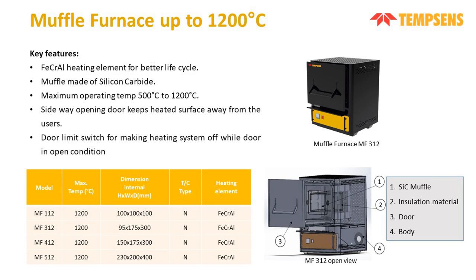Then you can see in the image the MF312 open view. You can see we have a door opening to the side of the furnace with a limit switch for safety reasons, to shut off the furnace when the door is open. And coming to the models, we have four models in the muffle furnace. Majorly the models are differentiated according to the dimension. The temperature is the same for every unit; its maximum is 1200 degrees Celsius. The thermocouple we have used in the muffle is an N-type thermocouple, and the heating element selected is FECRAL.